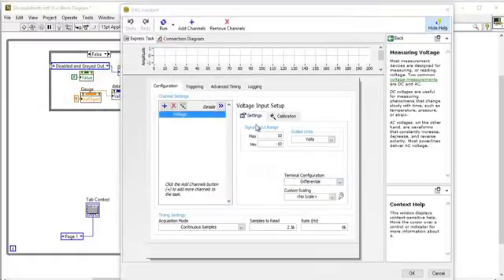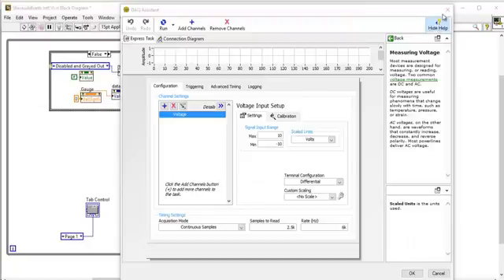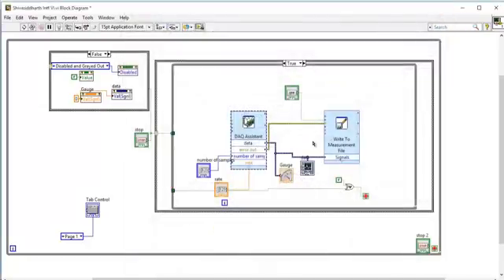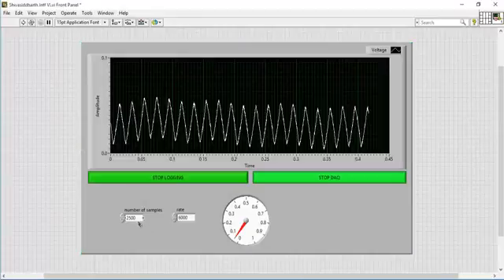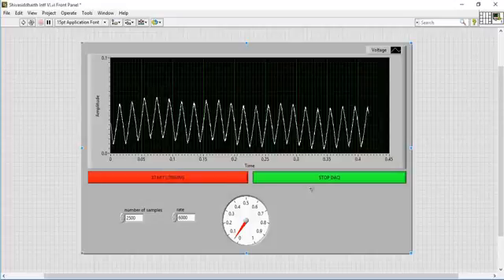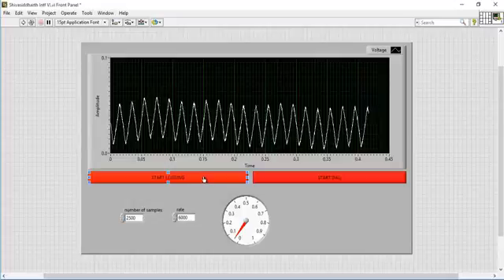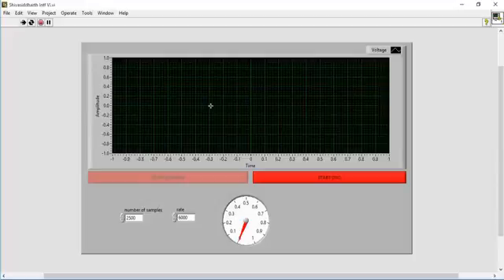You can see here the data logging acquisition mode is continuous samples. When I set N number of samples, the number here doesn't matter as continuous data is being logged at the rate of 6 kilohertz or 6000 Hertz. The number of samples becomes the buffer size for the data logging and for your chart reading.